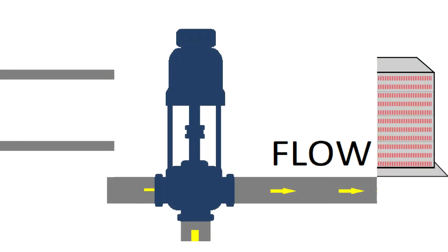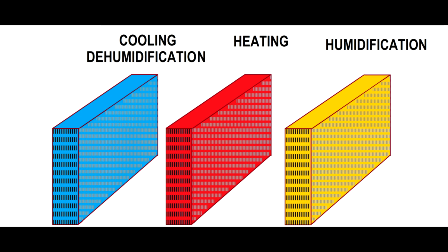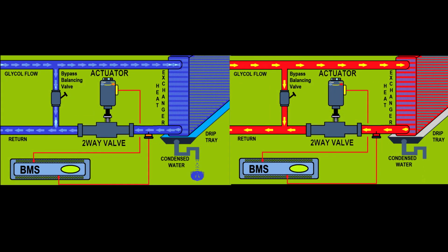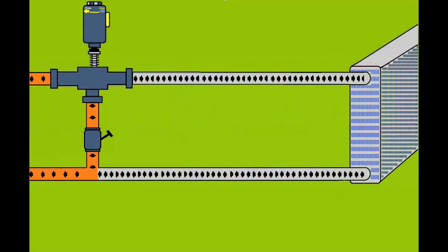Going further with this, you'll observe that the valves are not always 0 or 100%. They can be proportional, a PID. So this valve will allow more or less cooling or heating agent to pass according to the heat demand. That will give you better control. So the cooling, heating and humidification coils will be controlled by these actuators. You will see this one a little bit later and it will make more sense to you. A building management control will control the actuators that allow the heating or cooling agent to pass and to cool or heat a heat exchanger that will further cool or heat the air.